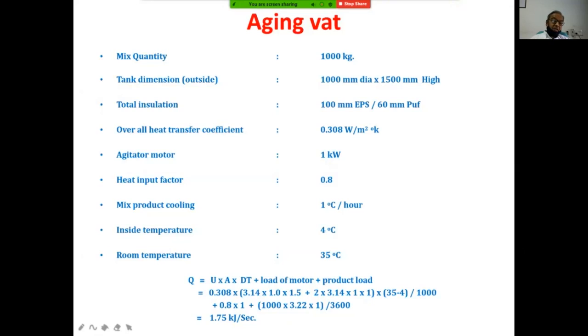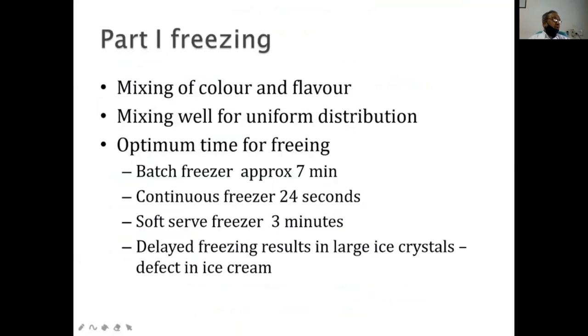And again, 0.8 is the motor load. So 0.8 into 1 kilowatt is considered the heat load of the motor, and the product cooling load is considered. And if we get 1.75 kilojoule per second, then 1.75 kilowatt is the load. So here we only have to consider heat gain from the outside atmosphere, plus the heating load of the agitator by stirring, and the product cooling, which is required at 1 degree per hour. Now, part one of making the ice cream from this liquid mix.